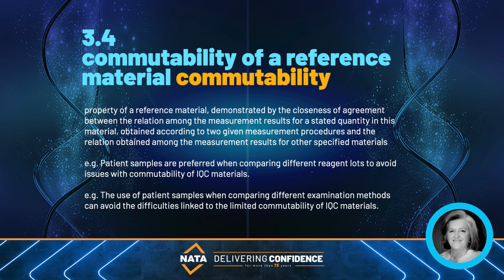Patient samples are preferred when comparing different reagent lots to avoid issues with commutability of quality control materials. This could be extended to the preferred use of patient samples when verifying new equipment. This is an issue labs have and a common assessment finding.